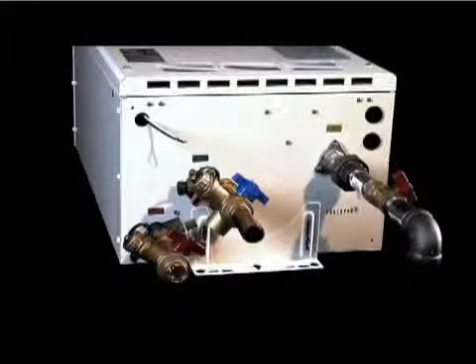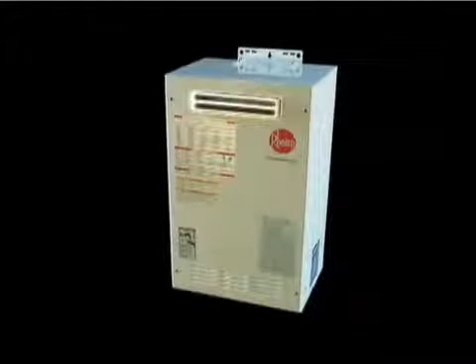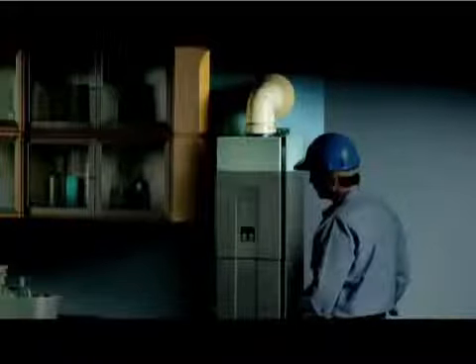When hot water is called for by an appliance or a faucet, cold supply water flows into and through the unit. A sensor detects the flow, triggering a computer-generated signal to send propane to the heating element and bring combustion air into the inducer motor. This exterior unit draws combustion air from the intake at the top and exhausts it from the louvered vent near the bottom. Units installed inside require a sealed combustion direct vent pipe that both brings in and exhausts combustion air safely from and to the outside.